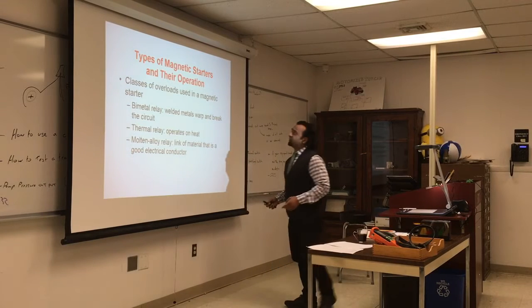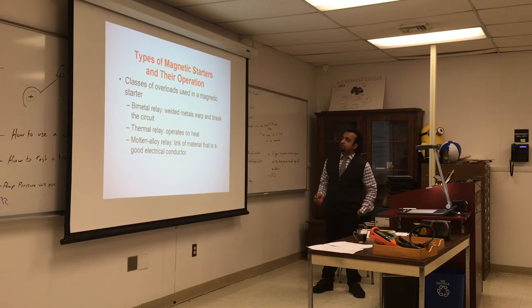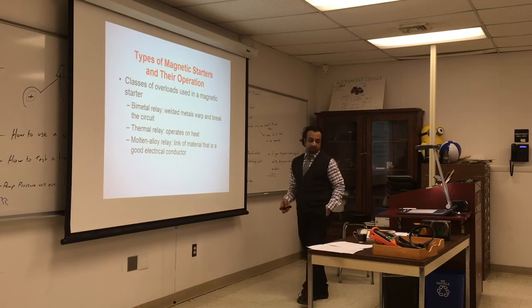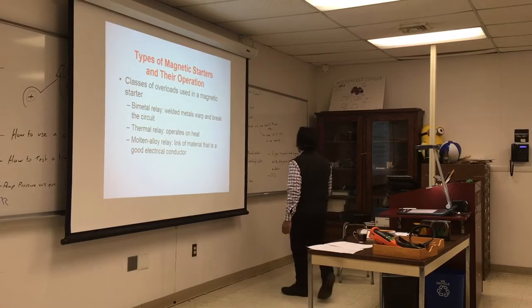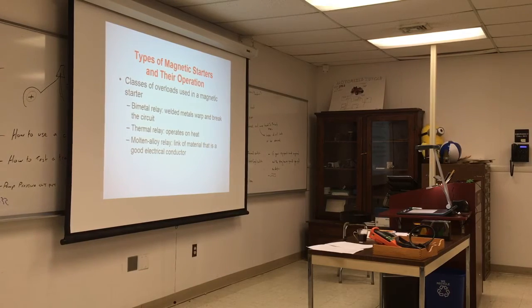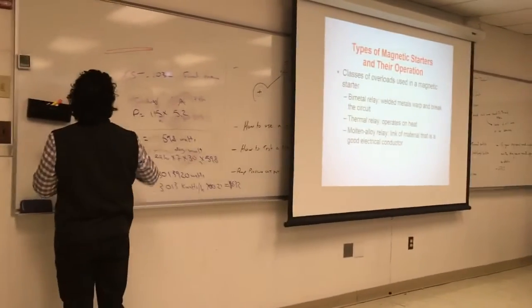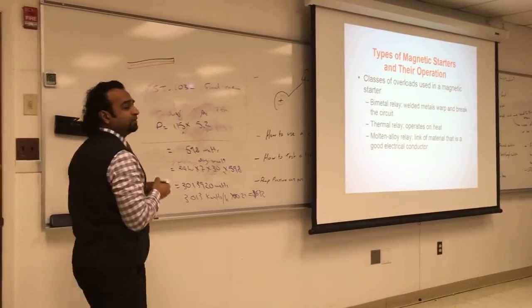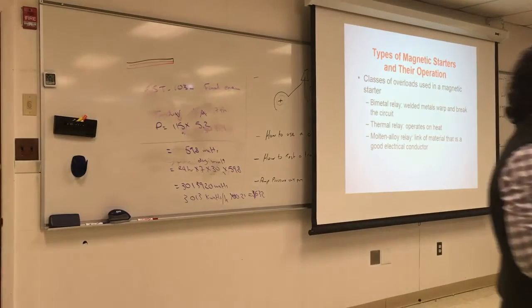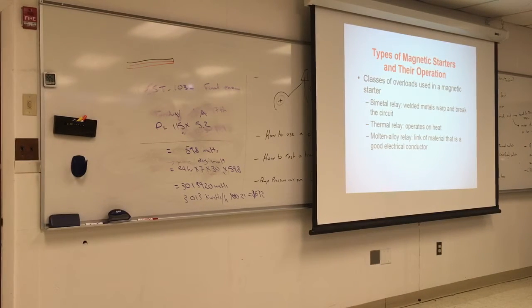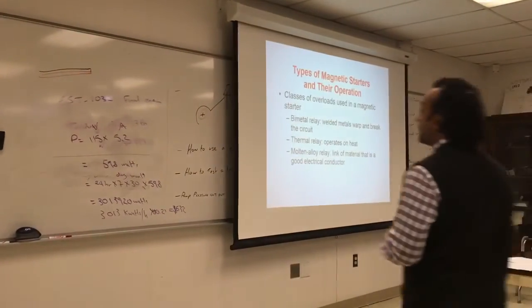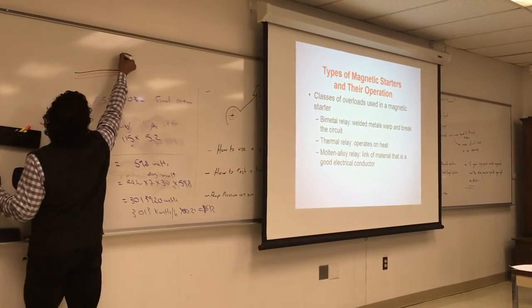So these are some types of magnetic starters. They have a bimetal relay, which is welded metals that warp and break the circuit using heat. How does that work? If I put two metals together, and this technology has been around for a while, two different metals with different properties, and I heat them, are they going to shrink and expand at the same rate? No, and that's the purpose. If they don't expand at the same rate, what will happen? It will bend. One of them will be shorter than the other.